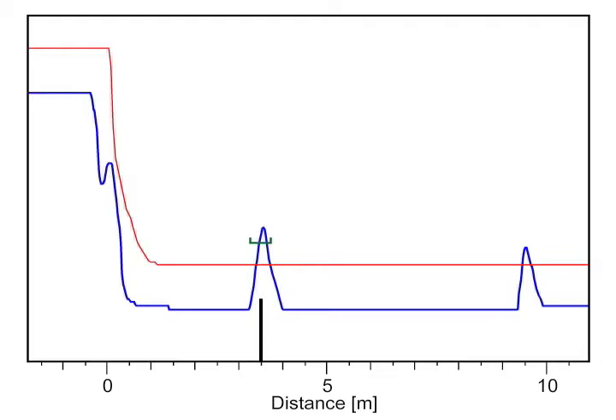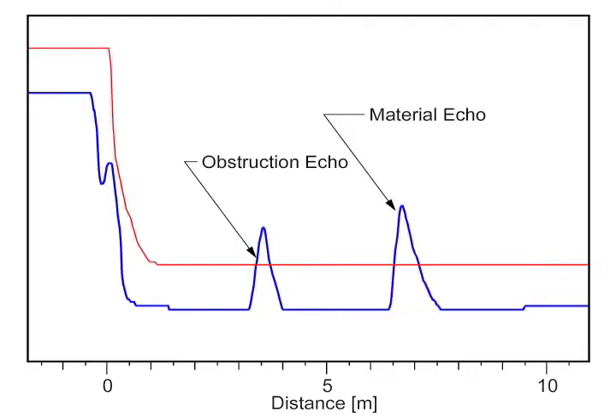How can we eliminate this risk and have the level device ignore the obstruction echo? The answer is Auto-False Echo Suppression. With Auto-False Echo Suppression, we can teach the level measurement device to automatically ignore the obstruction echo. It does this by shaping the TVT curve over the obstruction echo.